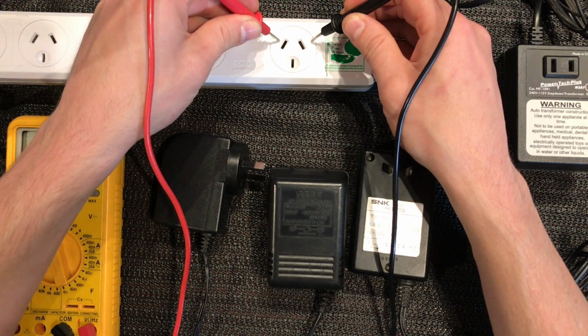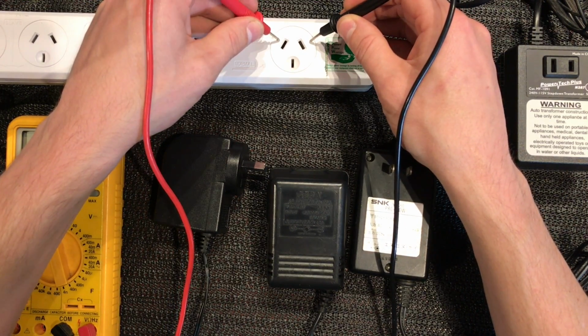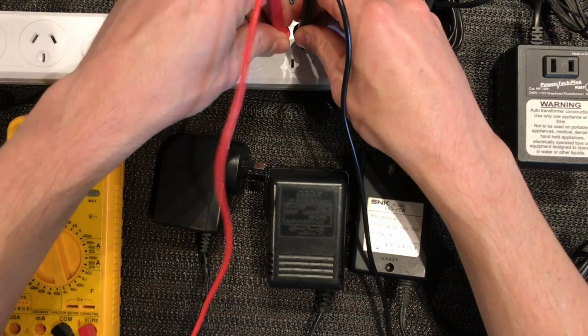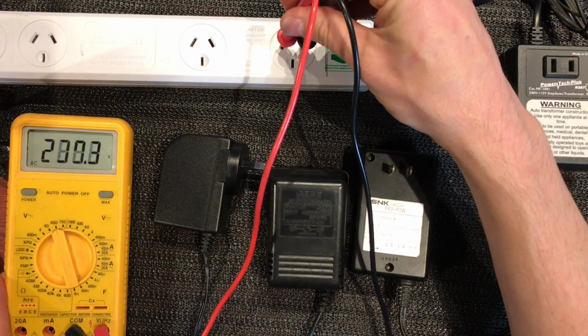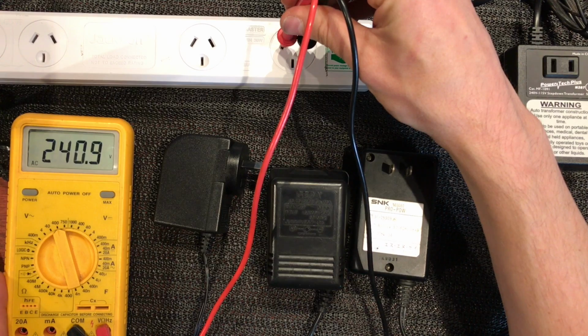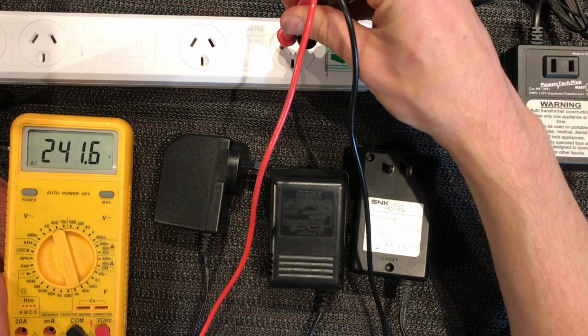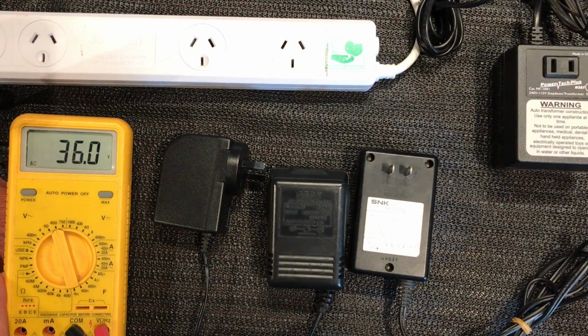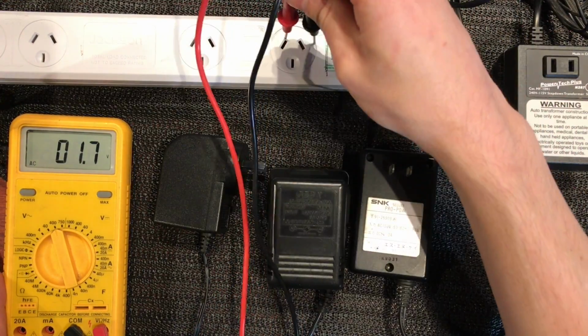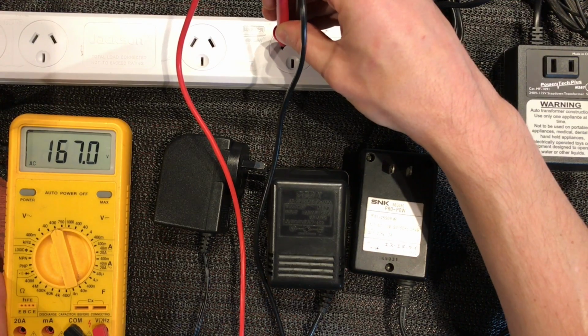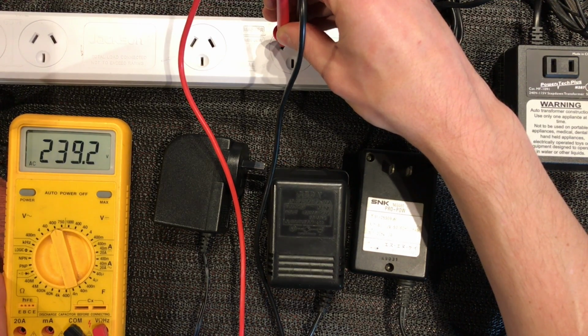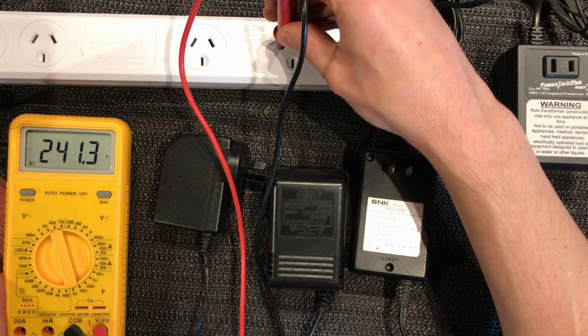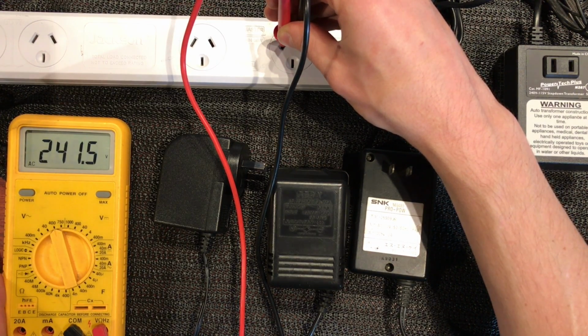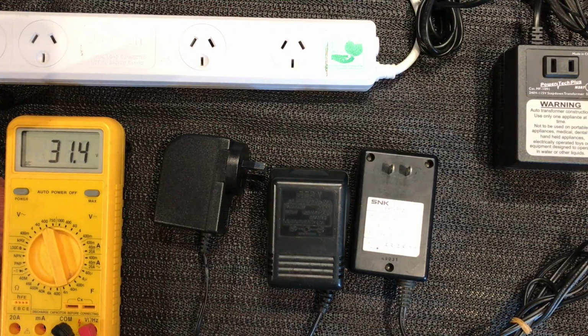Just be really careful doing this, guys, but take your time. Probes in, look at the screen. It'll go up a little bit slowly, and there you go. We're actually running a bit higher right now. This number will fluctuate throughout the day depending on the load on the lines and things, so you might measure it and it might be different at that particular point in time. It's running a little higher today, to 241.5. So that's what we've got coming out of the wall.